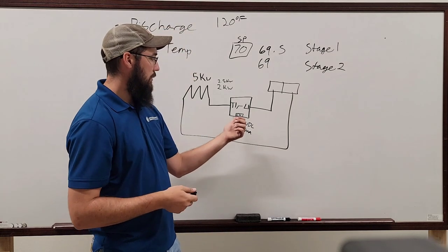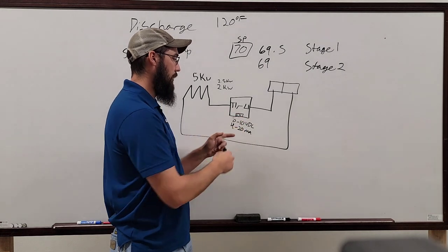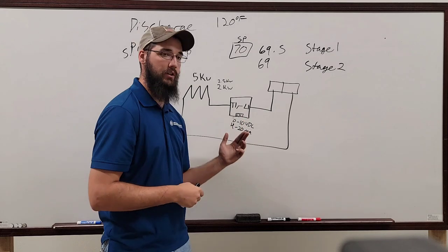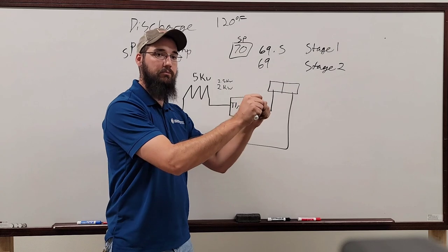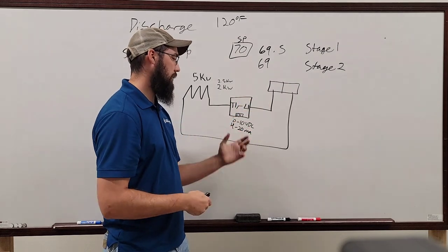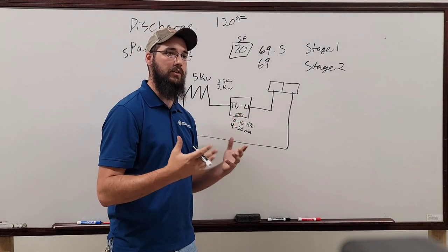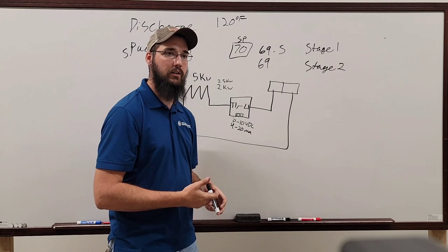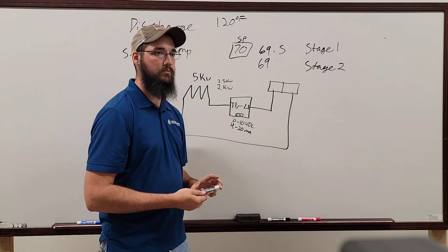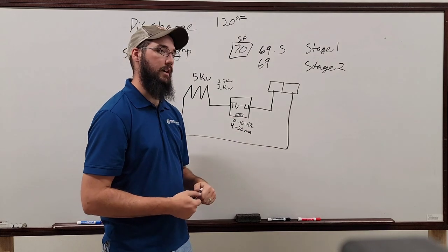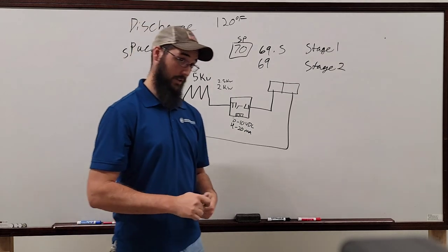At the end of the day, what you can do is take a reading and see, am I getting a control signal here? Now, 0 to 10 volts DC is really easy to take that reading on; you just read it. With 4 to 20 milliamps, you have to put your meter in line with that signal to see how much is getting fed. Would it matter, is there a polarity there? You'll want to put it on the input side, the positive side instead of the negative.